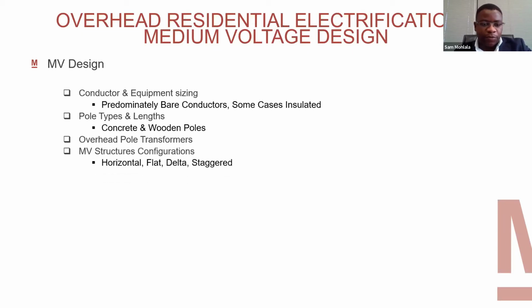MV structures and configurations - horizontal, flat, delta, and staggered - also need to be guided by your supply authority. One or two of these can be used, but supply authorities normally have a preferred configuration for overhead networks, so you'll need to liaise with them to ensure you're designing to their standards and that they're happy with it.